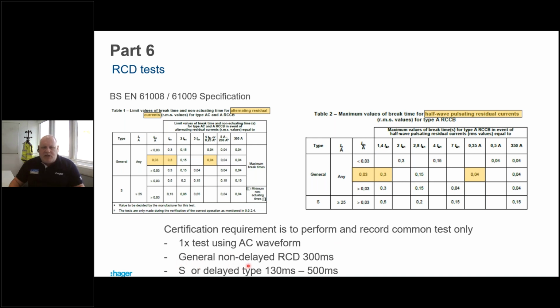So a general non-delayed RCD, we need that to trip within 300 milliseconds. That would be for a 30 milliamp device. An S or delayed type, we're looking for that to go within 130 milliseconds and 500 milliseconds. So testing has become quite a lot simpler on RCDs, certainly for certification purposes.